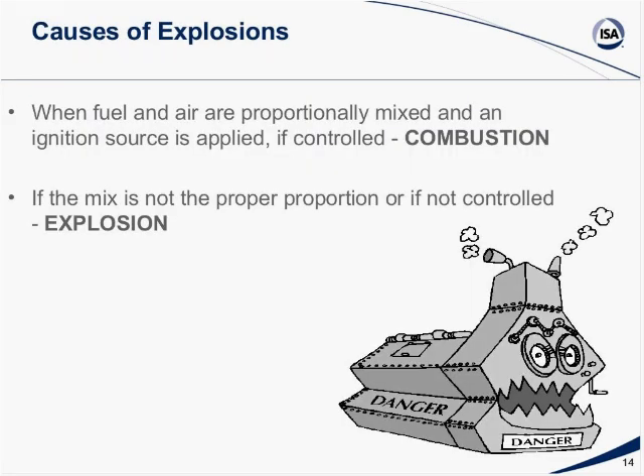Very simply put, when fuel and air are proportionally mixed and an ignition source is applied, if controlled, you have combustion. In other words, if you have a good fuel-air mixture in the right proportion, you're going to have combustion. If the mix is not in the proper proportion, or if not controlled, you're going to have an explosion. At any time the air, fuel or igniter come in the wrong sequence, you're going to have an explosion. Now, some people say a puff is not an explosion because it did not do enough damage to shut down or prevent the system from running, but it still is an explosion.